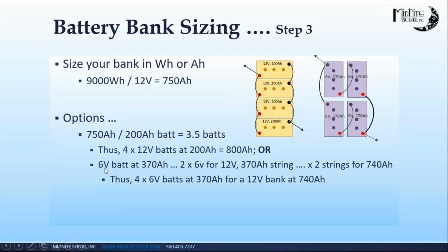Or I have these 6-volt batteries, found at 370 amp hours. These are commonly like L16 batteries, about twice as tall as a regular car battery, very common in the solar world - you'll see them at 6 volts between 370 and about 440-445 amp hours. So I get 2 of these in a 12-volt, 370 amp hour string. I need 2 strings, which gives me 740 - pretty close to 750. So I can go for the 12-volt batteries at 200 amp hours, or the 6-volt batteries at 370. Either bank is almost the same: this one's 800 amp hours, this one's 740. We'll call it apples to apples.